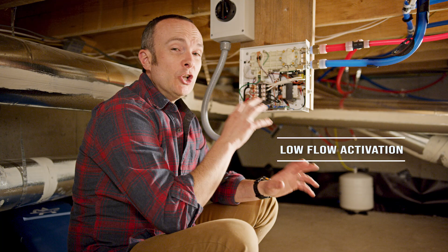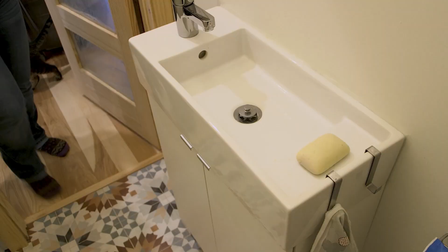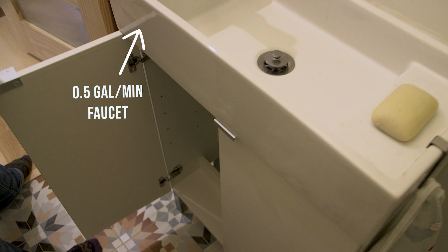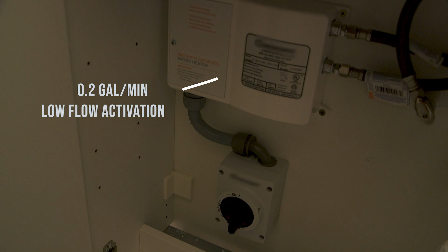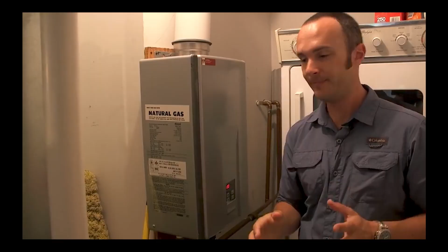One other thing about this is that it has a low-flow activation. This is something to watch out for with any tankless technology, including point-of-use. For example, the sink in our powder room is half a gallon a minute, one of the water-efficient fixtures in the house. If I turned that all the way on hot, some bigger units that serve an entire house won't even register that you want hot water.